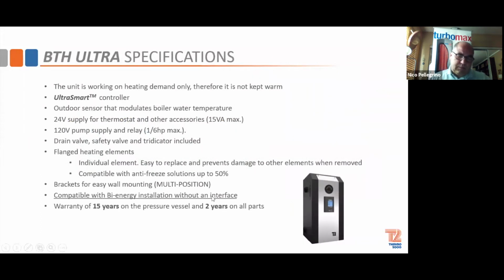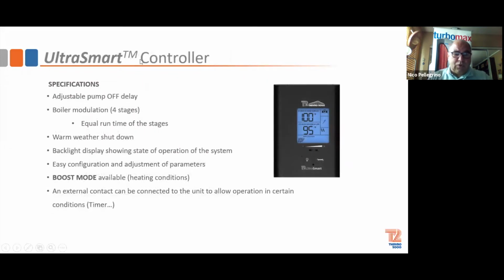What a lot of contractors like is you do not need a primary-secondary for our boilers. That's less piping and a really nice configuration in small areas. 15 years on the pressure vessel and 2 years on parts. As I was saying about the controller, it has an adjustable pump off delay. Also, the boiler has equal runtime per stage. Each boiler comes with outdoor reset. The backlit display shows the state of operation in the system. You'll see it right in front of you, great for troubleshooting. I can see a lot just by a picture of what the controller says, what the boiler is or isn't doing. So it's really good.